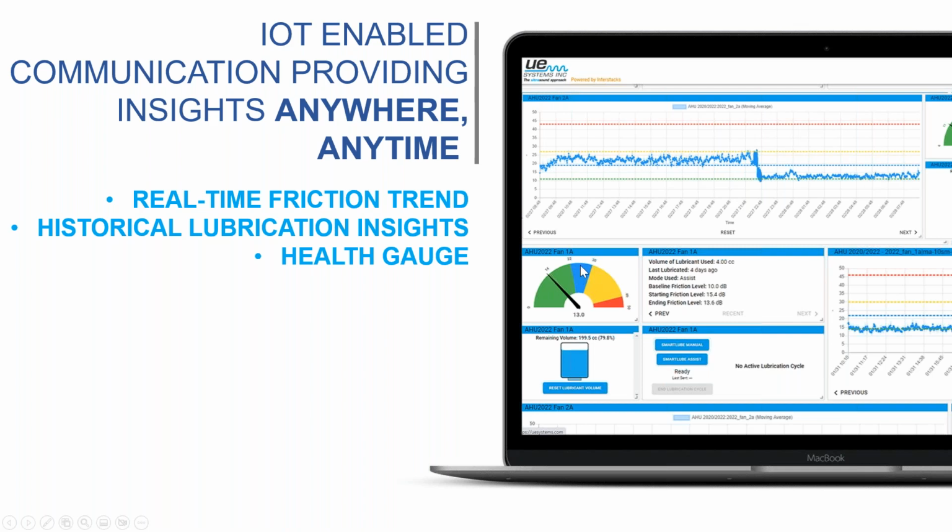So what happens if, just like on the Stribeck curve, you hit 14 and you keep on adding grease? Guess what? That arrow will come back. In fact, what we have seen, the rate of rise, which I showed in that chart, is a lot different. So typically it will go past the blue and into the yellow.